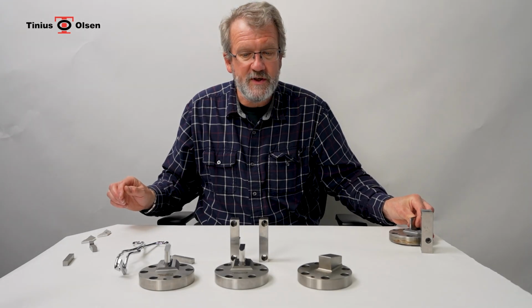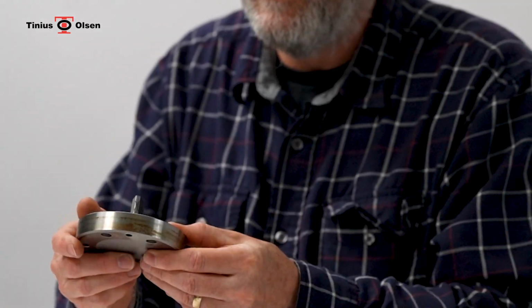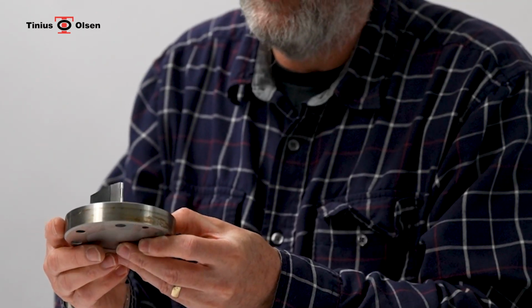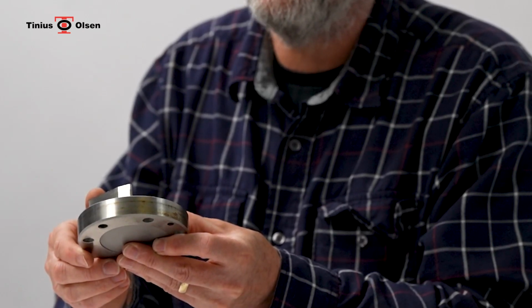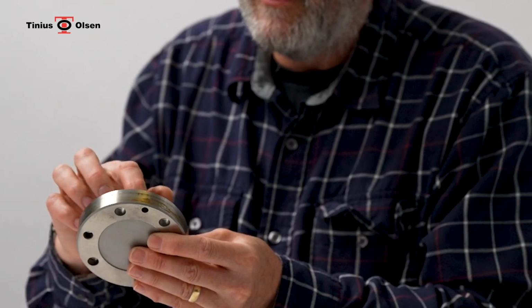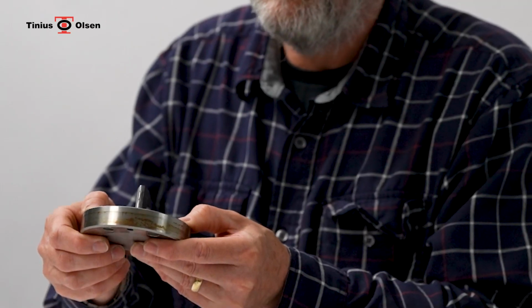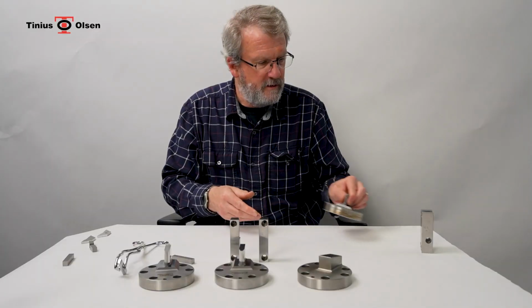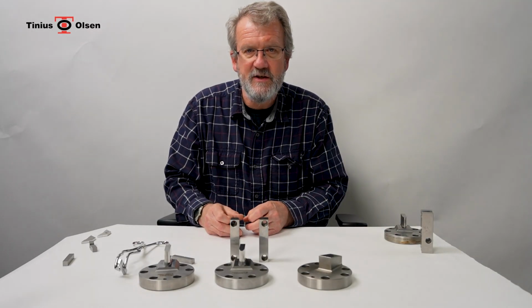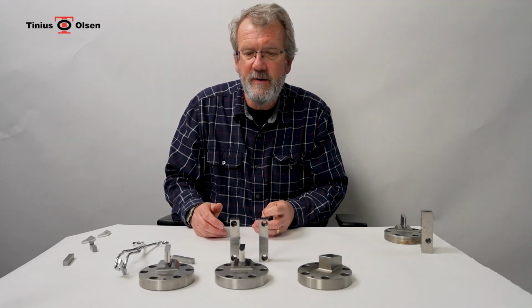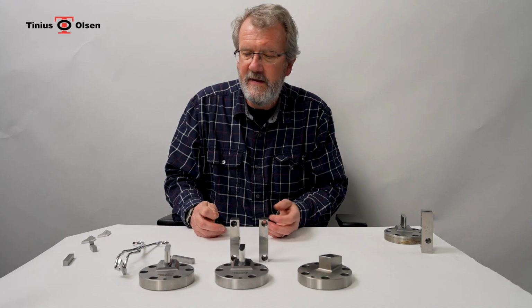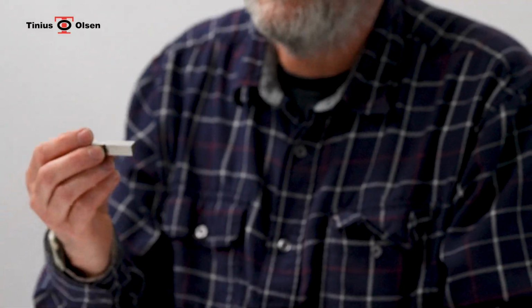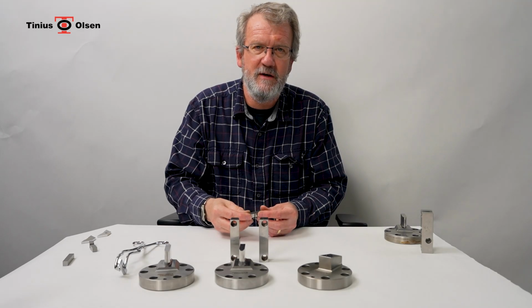The strikers also leave an impression, and this striker here has a failed striker corner, and it is possible to see with the naked eye a witness mark on the side of here showing that it has worn. There is some hourglassing on the front, which skilled technicians will see and identify as potential wear, requiring that the anvil be replaced. All these items can be ordered and then replaced. Technicians typically would do this work. However, anybody who has the calibration experience can do it, and then the standard reference materials are required to break to complete the calibration of a machine.